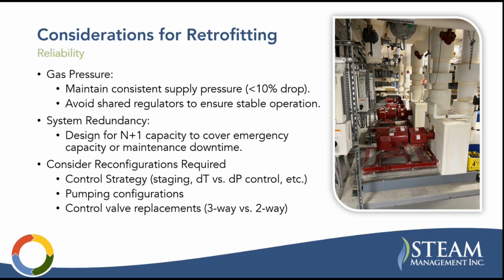System redundancy, again, N+1 capacity is great. And using multiple boilers is going to be good for staging. You want to consider the reconfigurations required, which we'll talk more about. But you have control strategy, your pumping configurations, and your control valve replacements, to name a few.